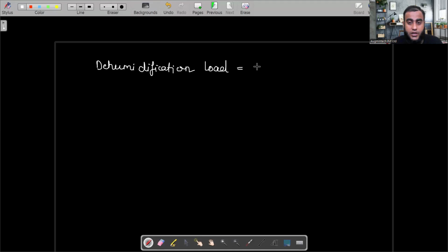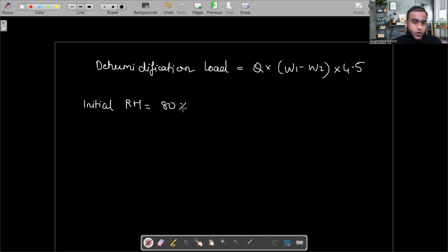So now, let me know, the formula is the same: Q, W1 minus W2, into 4.5. Now suppose, I'm just assuming, here also the same, we are designing for an office building, the building type is office building. Suppose the initial relative humidity is 80%, I'm assuming, for any location. And the desired relative humidity we have to maintain is 50%, let's say, and the dry bulb temperature, you know, is the same, 75 degrees Fahrenheit. So if the initial relative humidity is 80%, that is why we are using a dehumidifier here, because we have to remove the excess moisture from here.